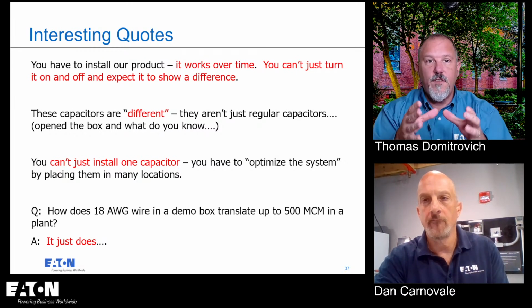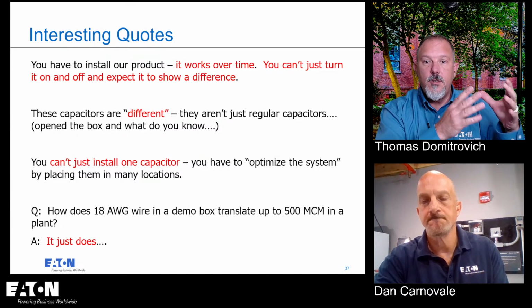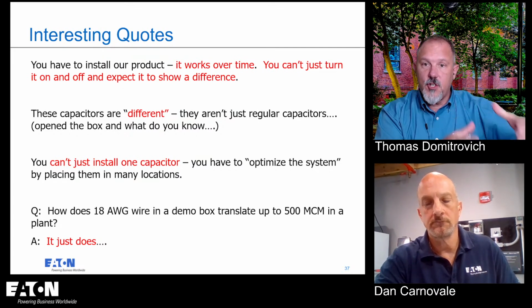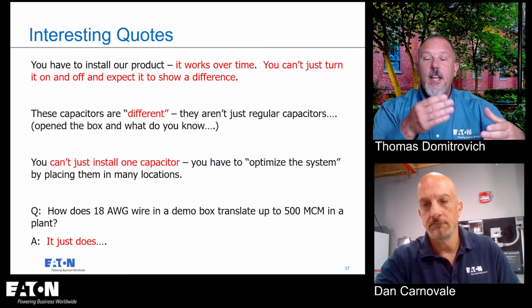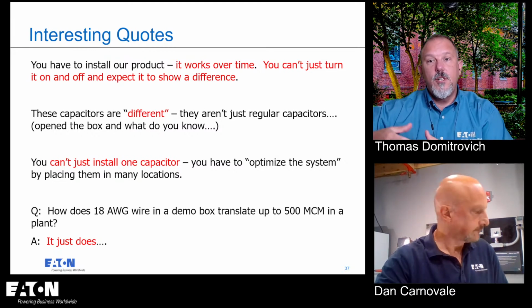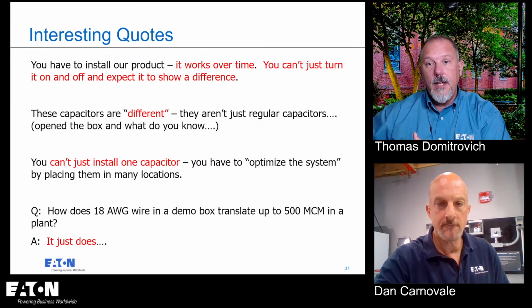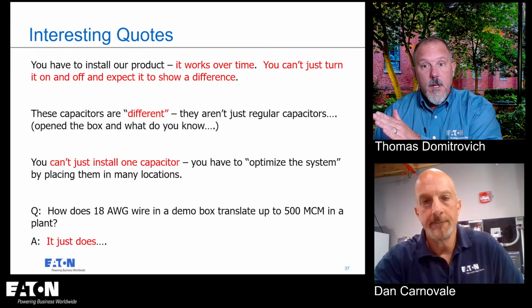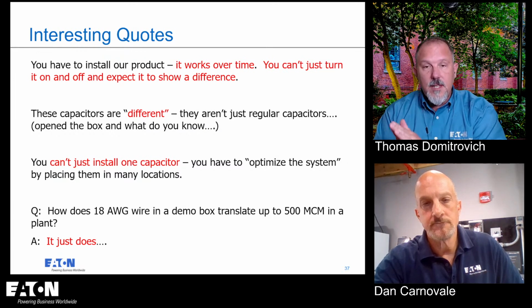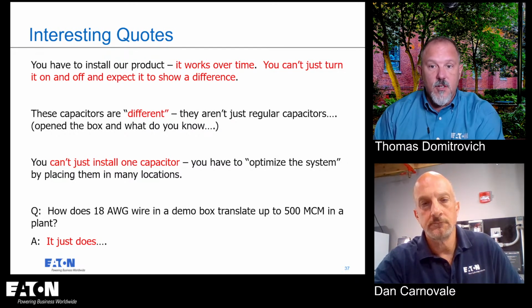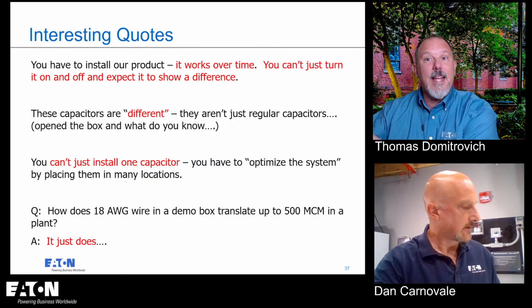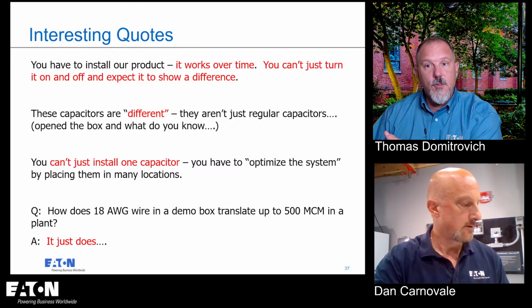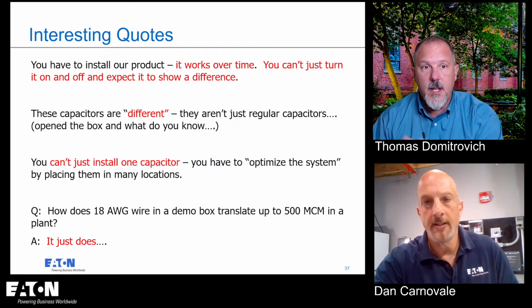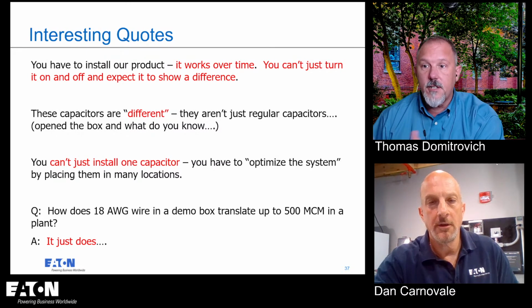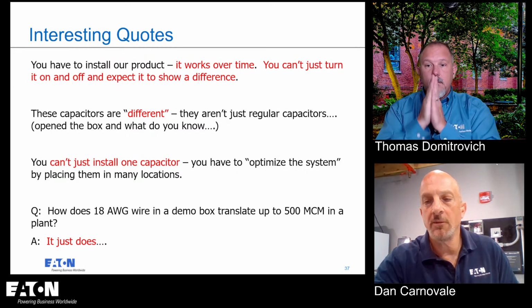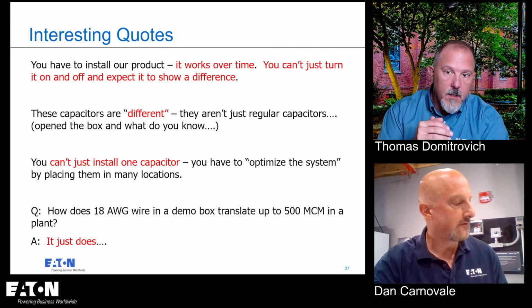I've seen this done. If you have a transformer of a certain kVA rating, and I have to put more load on it, I could put a power factor correction capacitor on the secondary to reduce my kVA. I'm not changing the watts, but I'm reducing the kVA, so my transformer can still supply that, and I could pull less amps downstream, using less of the percentage of my conductors and whatnot.